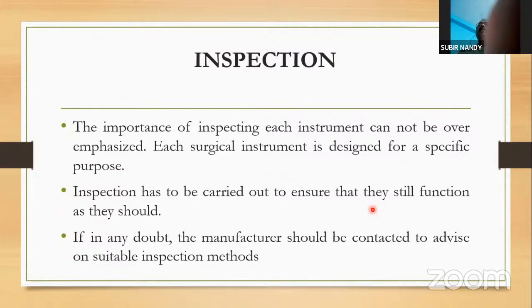Inspection. The importance of inspecting each instrument cannot be overemphasized. Each surgical instrument is designed for a specific purpose. Inspection has to be carried out to ensure that they still function as they should. If in any doubt, the manufacturer should be contacted to advise on suitable inspection methods.